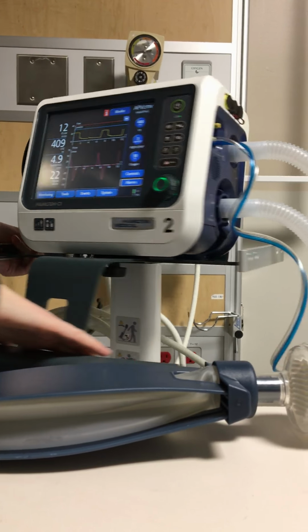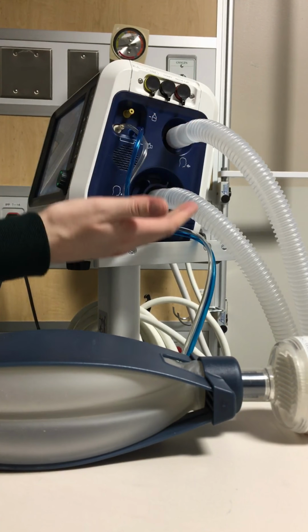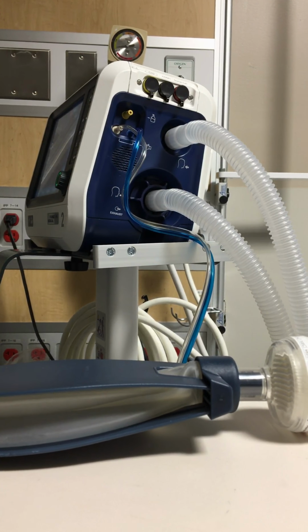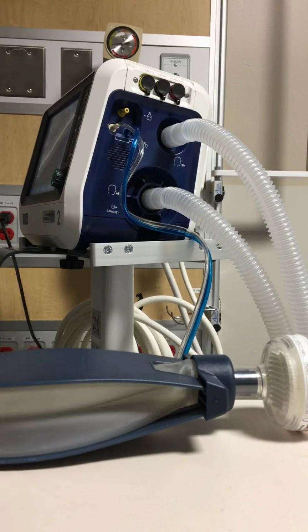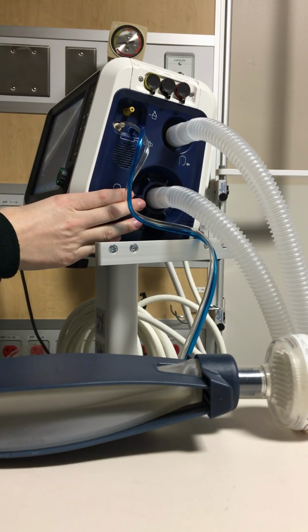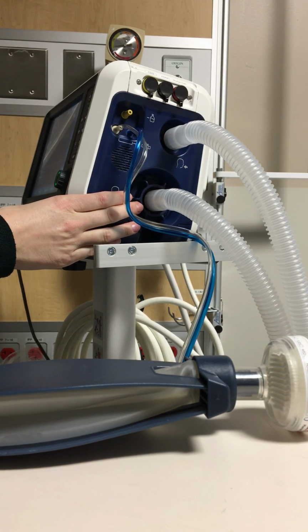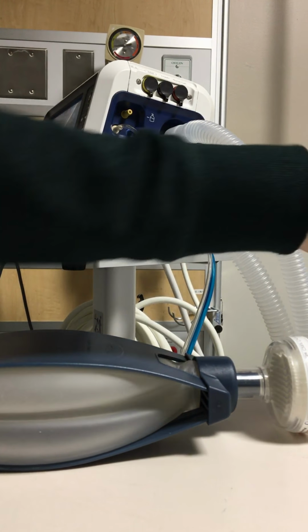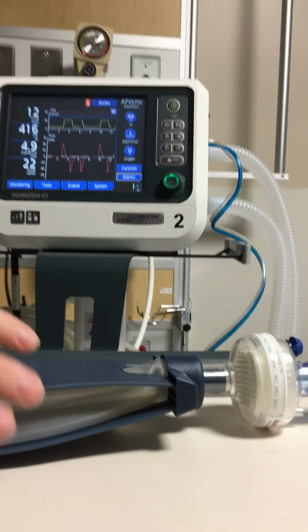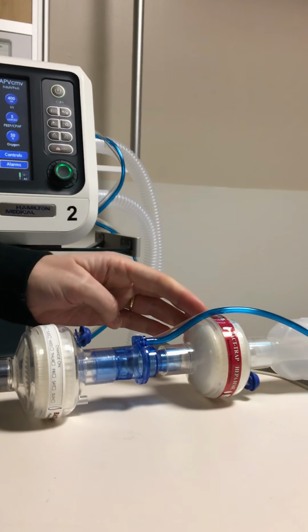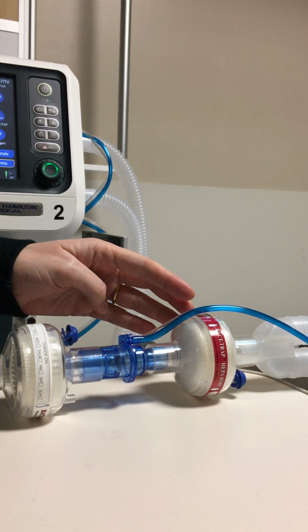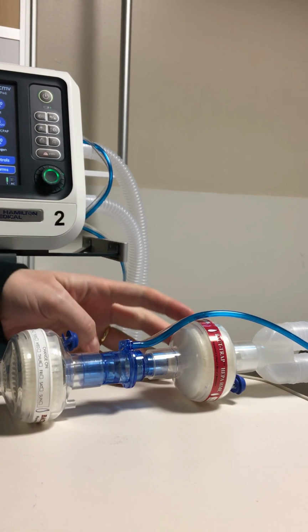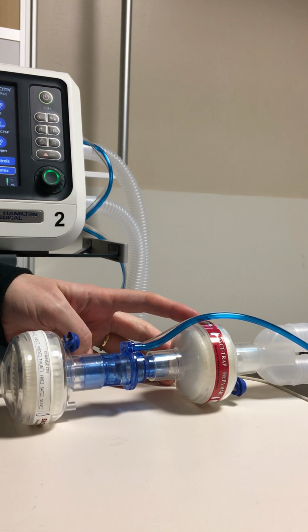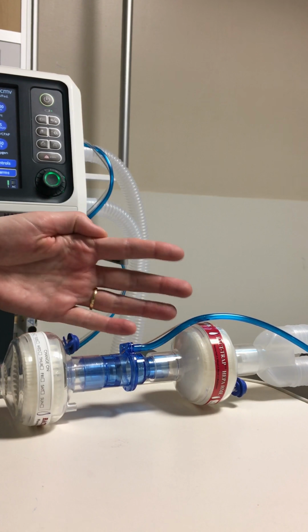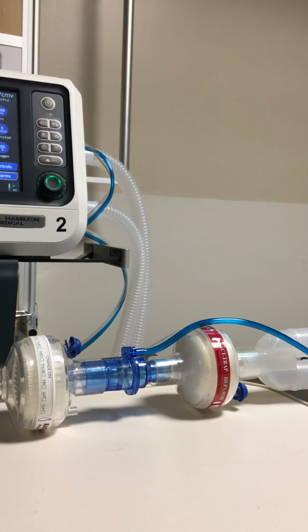On the other side of it, you will see it has a dual limb circuit and the flow sensor attachment there. We also have the expiratory valve that is here, and the circuit will come all the way up to our patient with an HME, a heat moisture exchanger. Therefore, it does not need a heated circuit. The patient is getting their own heat and moisture back from their breath on the next breath.